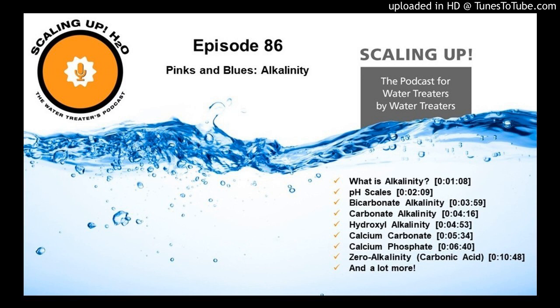A lot of times when I'm working with other water treaters or other companies that have some sort of problem, normally pitting, it's because they're using the wrong chemistry for the alkalinity that they have in their water. So it's very important that us water treatment folk understand exactly what alkalinity is.